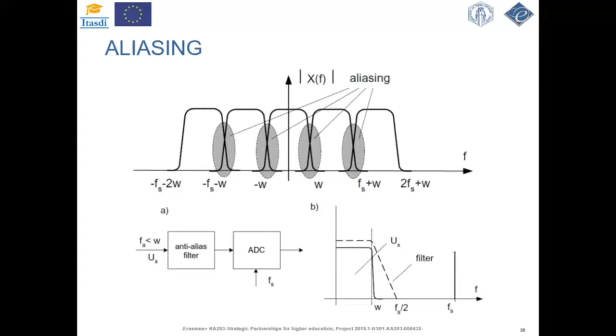On the other hand, the parameters and the type of the anti-aliasing filter must be appropriately defined according to predefined criteria. Among others, there are three basic filter types: Bessel, Butterworth, and Chebyshev. The Bessel filter has the smoothest phase to frequency and amplitude to frequency characteristic, but has low attenuation in the stop band. On the other hand, the Chebyshev filter has high attenuation in the stop band, but introduces ripples in the amplitude characteristic in the passband. The Butterworth filter has intermediate smoothness in the passband and attenuation in the stop band.